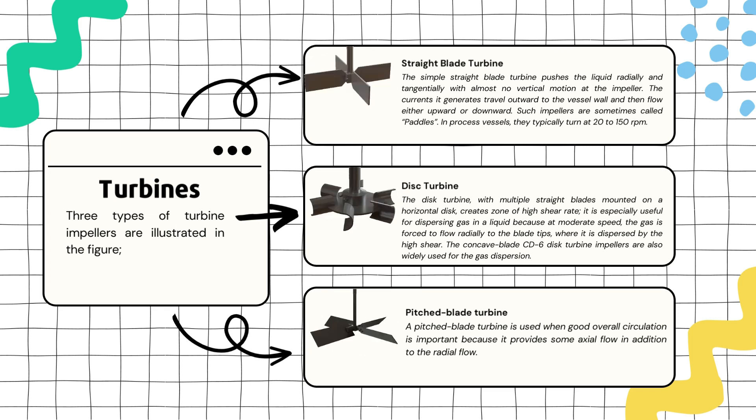The next type of turbine is a disc turbine. The disc turbine features multiple straight blades mounted on a horizontal disc. It's known for creating an area with a higher shear rate. It's particularly useful for mixing gases into a liquid because at moderate speed, the gas is forced to move radially towards the tip of the blades.